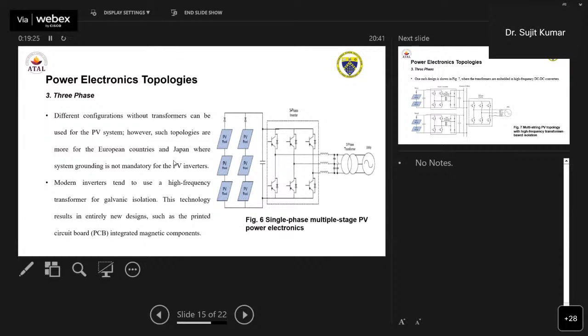Then there are separate configurations that can also be used without transformers. You can say that without using the transformers also you can use these topologies. These topologies are more utilized in the European countries and Japan. Why? Because there the grounding system is not mandatory for PV inverters. But in India, it is mandatory to provide the system grounding.